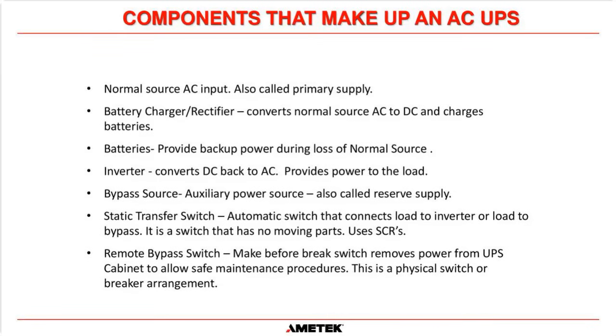All the terms are interchangeable, and that is usually unregulated power that comes directly from an MCC. It has no inverter behind it. It's just raw power from the grid. Then we also have a static transfer switch, and that is an automatic switch that connects the load to the inverter or the load to the bypass. And it's a switch that has no moving parts, which is why it's called a static transfer switch, static as in no moving parts. And it uses SCRs, which are silicon control rectifiers, to perform that function.